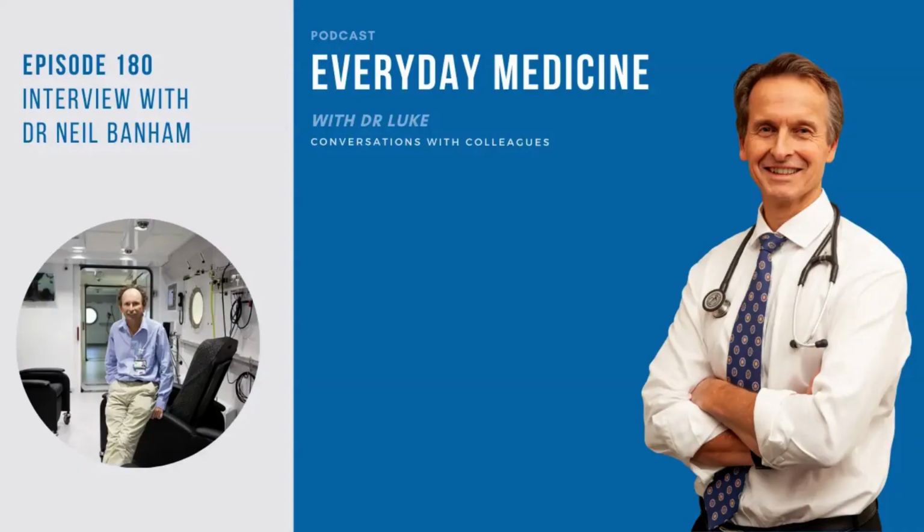I'll talk about, say, radiation cystitis, which there aren't a lot of other treatments for, and the other treatments that are out there, such as instilling alum or other nasty chemicals in the bladder, are not good, and cystectomy has a 30-40% mortality rate associated with it. So there are really no other good treatments at the moment that seem to be permanent for radiation cystitis. But we treat those patients for 30 to 40 sessions, 5 days a week. So that's 6 to 8 weeks. And that's about 2.5 hours. And we do that at 2.4 atmospheres absolute, or 243 kilopascals, or the equivalent of being underwater at 14 metres of seawater. So we've got 2 types of chambers.